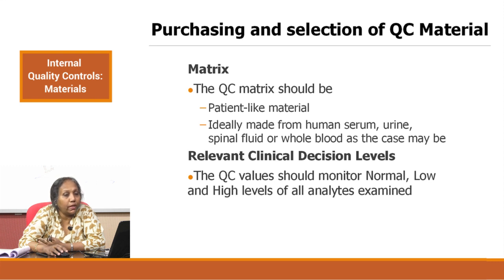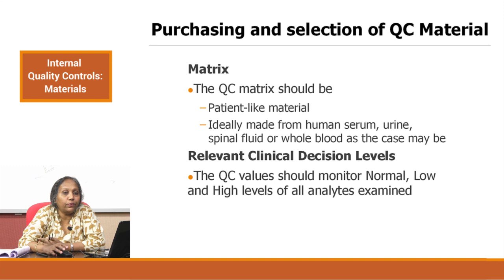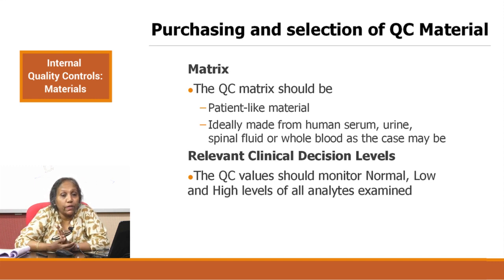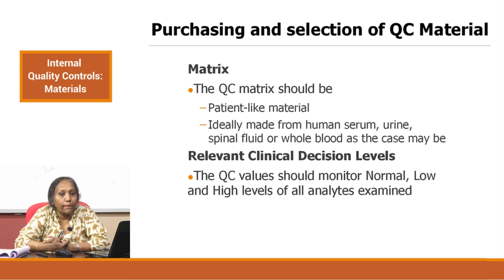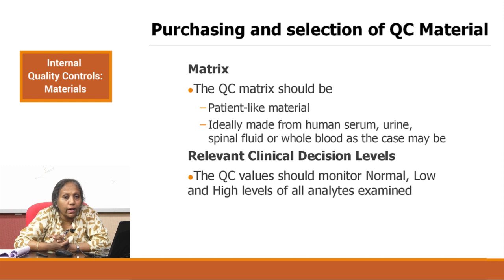If the sample is serum, the matrix should be like human serum. If it is a urine control, it should be like urine. If it is a spinal fluid control, it should be like spinal fluid. And if it is whole blood, the matrix should be like whole blood. The second consideration is relevant clinical decision levels — QC values should be able to monitor normal, low, and high levels of analytes that you are examining. Many controls like hematology controls and immunoassay controls have three levels: low, normal, and high. Whatever the clinical decision levels are, those levels should be monitored by the controls.